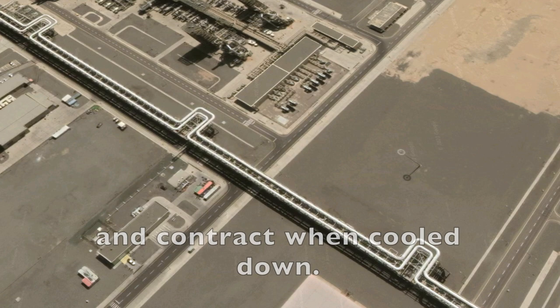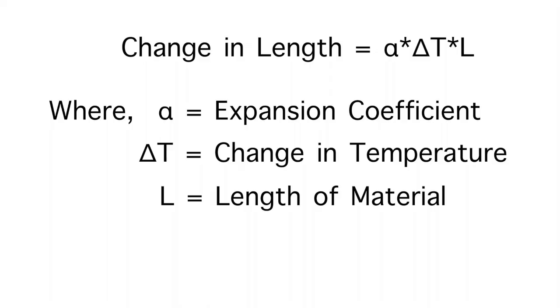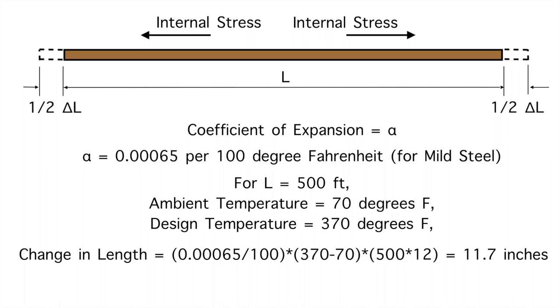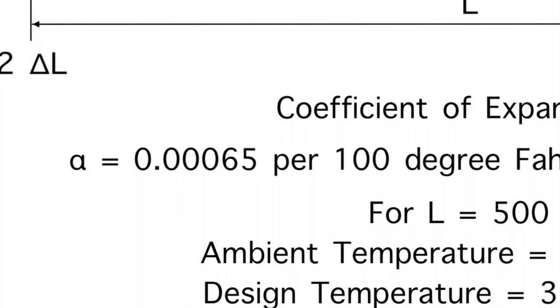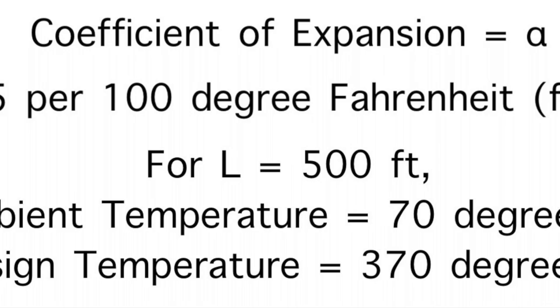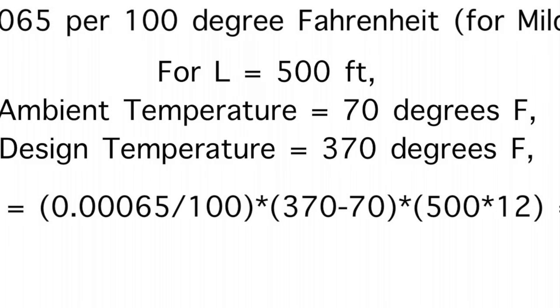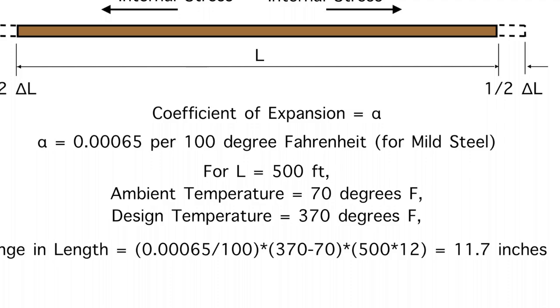We know from science that things expand and contract with changes in temperature — they expand when heated and contract when cooled down. The change in length is calculated using the formula alpha times delta T times L, where alpha is the expansion coefficient, delta T is the change in temperature, and L is the length of material. For example, mild steel has an expansion coefficient of 0.00065 per 100 degrees Fahrenheit. If you heat a 500-foot long pipe from a 70°F ambient temperature to a 370°F design temperature, it will increase in length by 11.7 inches, assuming the ends are free to move.